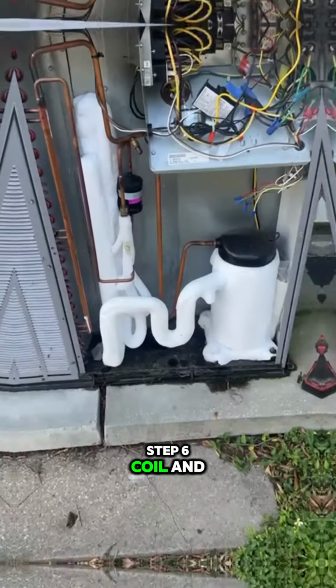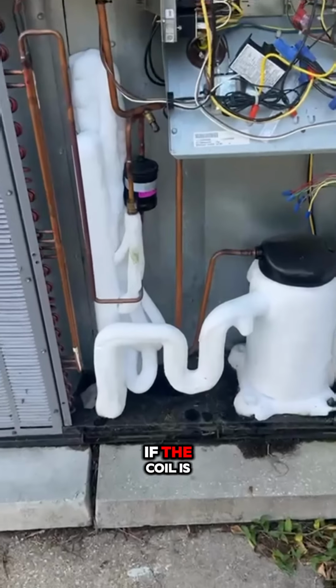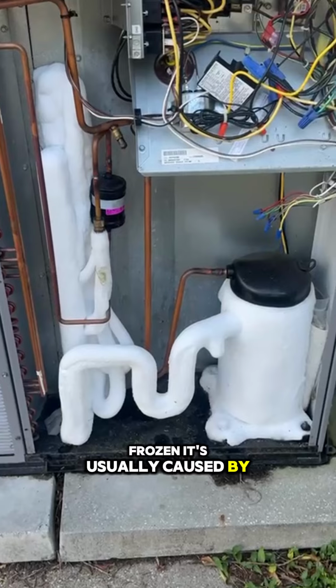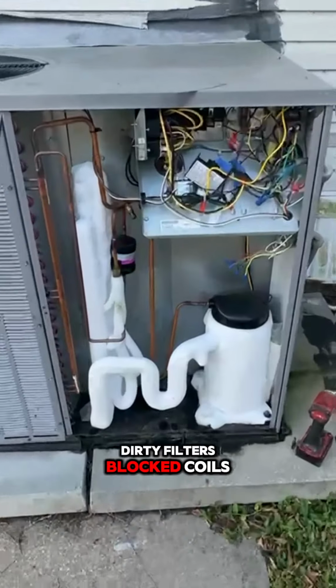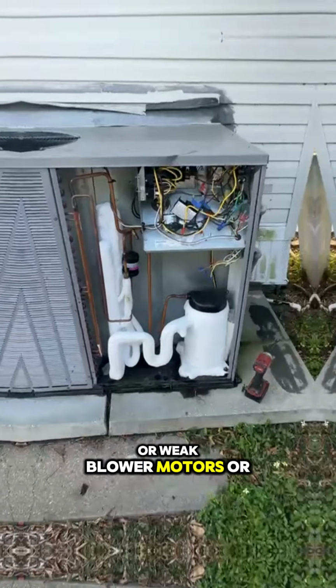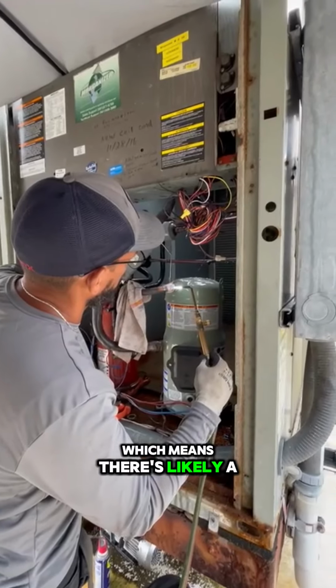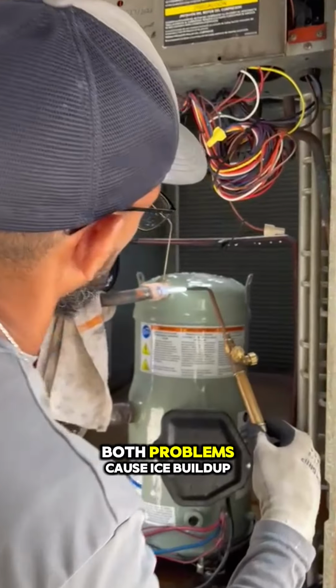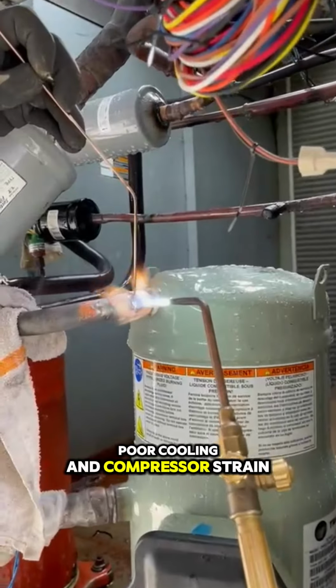Step 6. Coil and airflow issues. If the coil is frozen, it's usually caused by low airflow, dirty filters, blocked coils, or weak blower motors, or low refrigerant, which means there's likely a freon leak. Both problems cause ice buildup, poor cooling, and compressor strain.